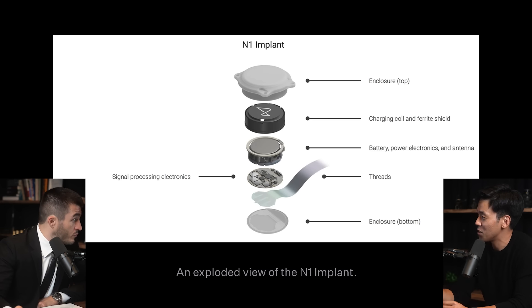There's a lot of innovation packed in to allow charging of this implant without causing that temperature threshold to be reached. Even small things like the charging coil and what's called a ferrite shield — without that ferrite shield, what you end up having with resonant inductive charging is that the battery itself is a metallic can, and you form eddy currents from the external charger, which causes heating and contributes to inefficiency in charging.